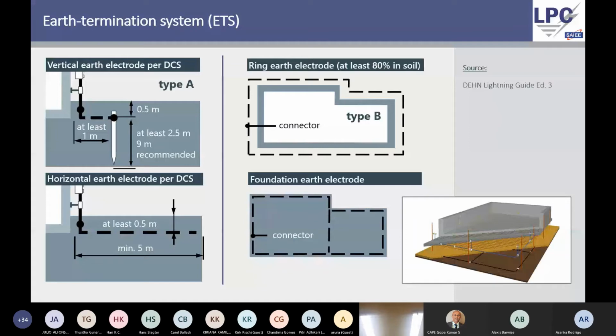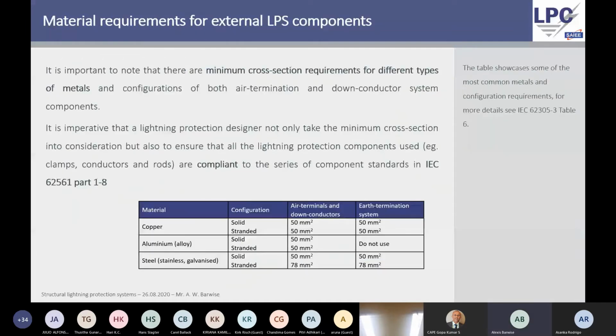Right. The material requirements, remember we said that the earthing system has the length, the shape, and the dimensions. So here we have a table that's given to us where we have summarized all three parts already. Air termination, the catching part; down conductors, the conducting safely and controllably part; and earth termination, the dispersing of it whilst minimizing dangerous conditions. If we use copper material of solid configuration, we see that we need a 50 mm squared cross-section for air terminals and down conductors, and the same for earth termination systems.